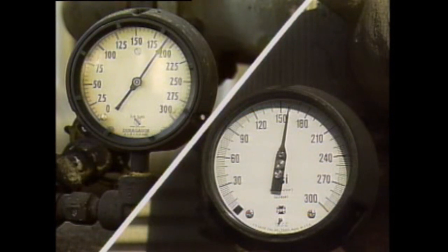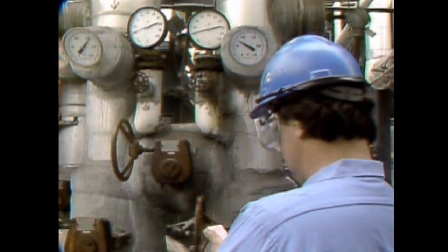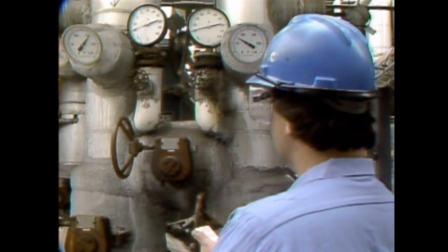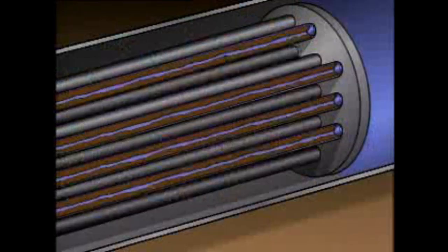In some situations, fouling can become bad enough to restrict the fluid flow. This problem may show up on the heat exchanger's instruments as an increase in the pressure drop or as a gradual decrease in the flow through the affected side of the unit. Fouling may also affect the temperature of both fluids passing through the heat exchanger. When fluid flow is restricted, the heat exchanger must be cleaned.